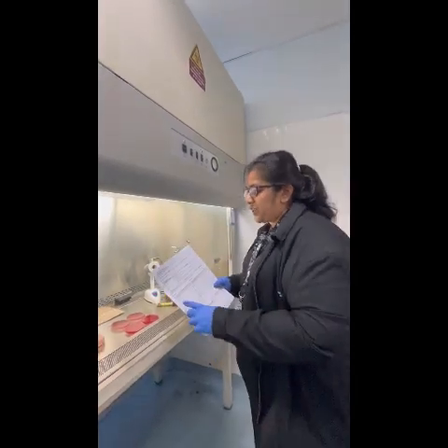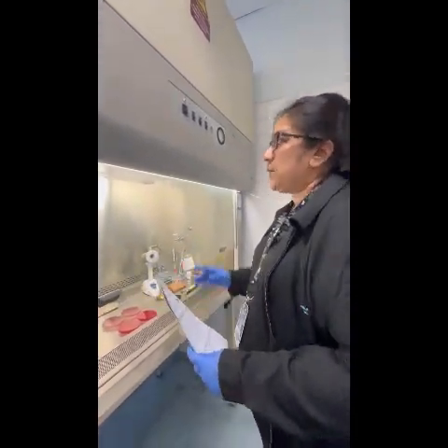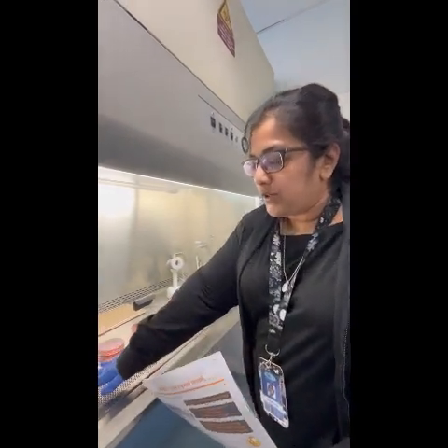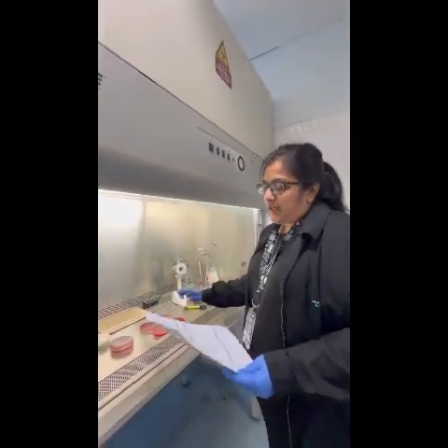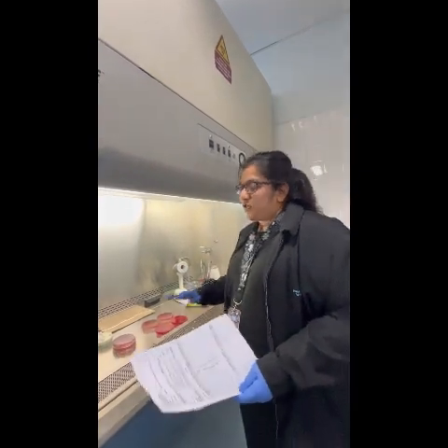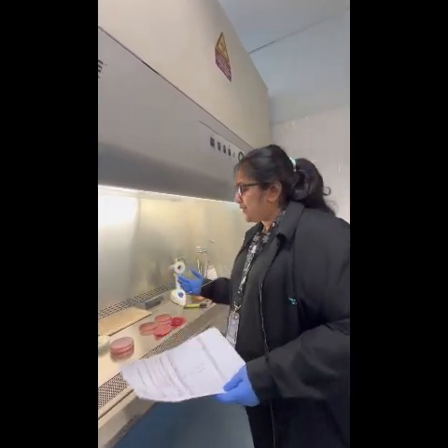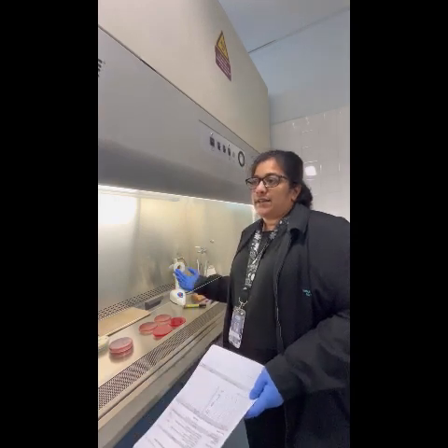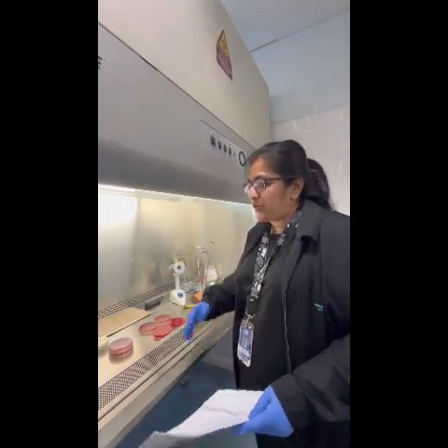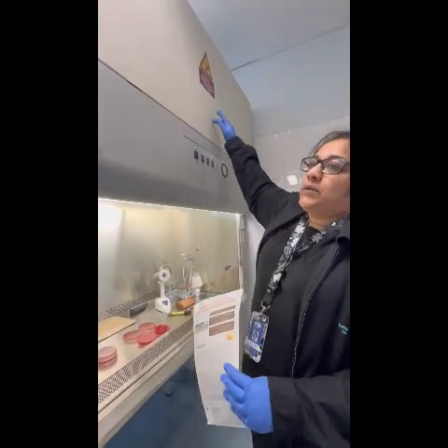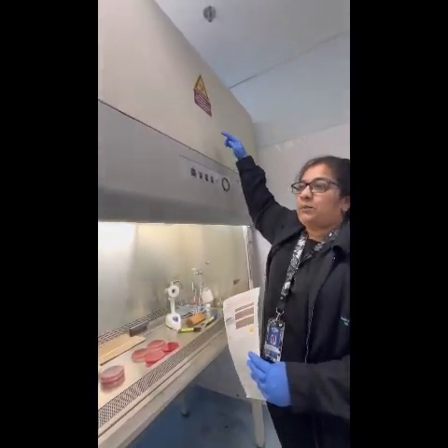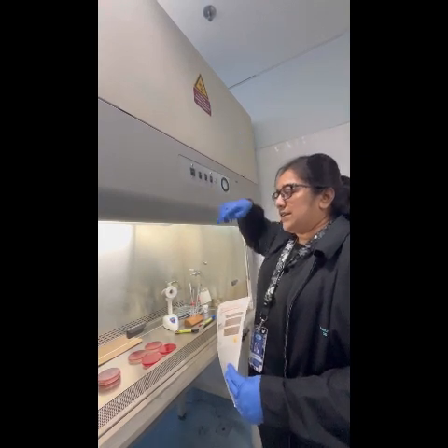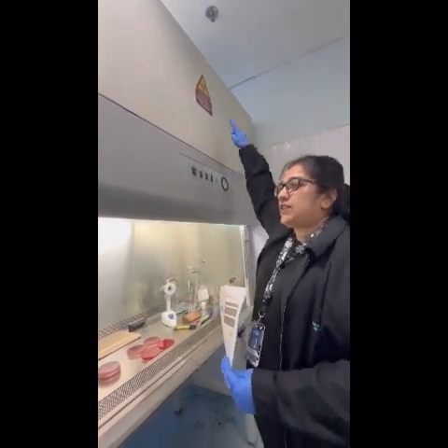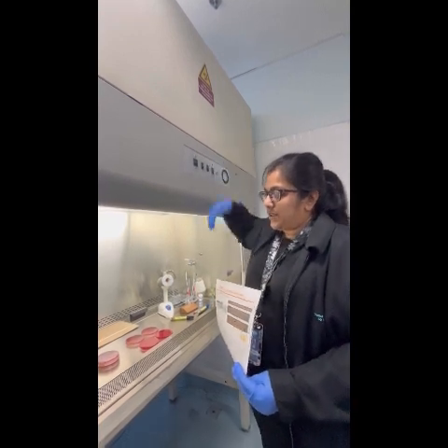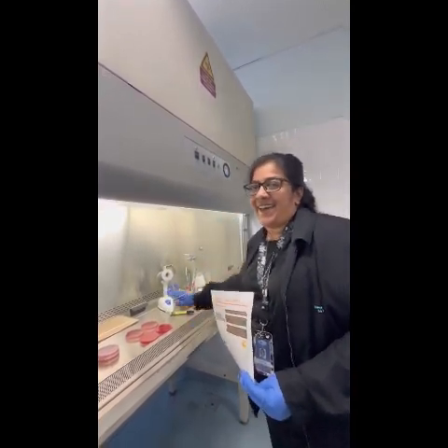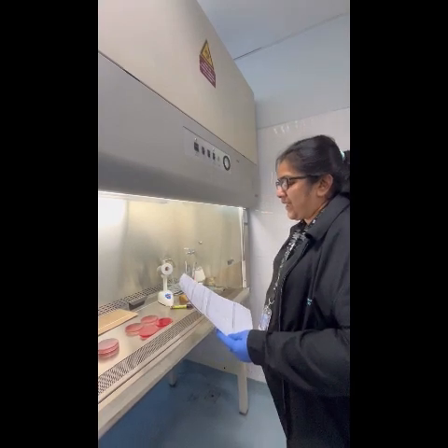As maintenance, we have a checklist of the things that we need to check. Number one is this blower. We need to ensure that this blower is on. What this blower does is that it traps the air inside the biosafety cabinet, not allowing the air to come out and air from outside to go in. Up here we have a HEPA filter, and this HEPA filter will recycle the air from inside here, filter it, and then send the air back down into the biosafety cabinet.